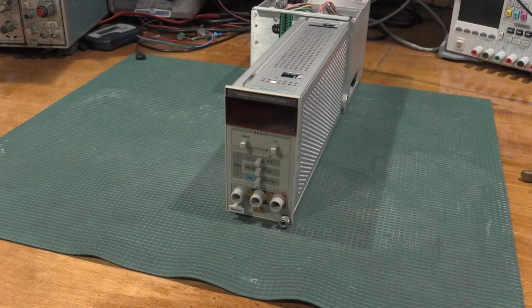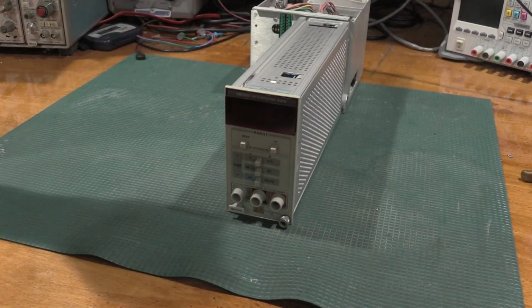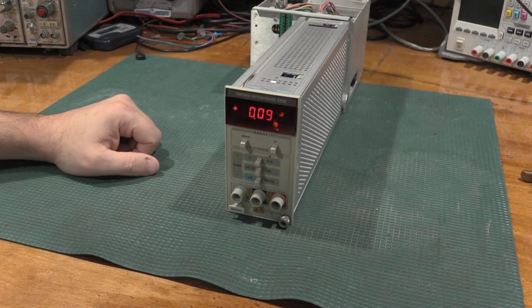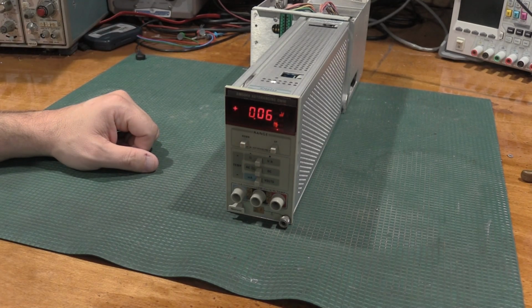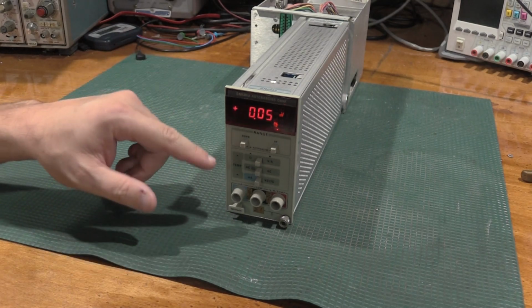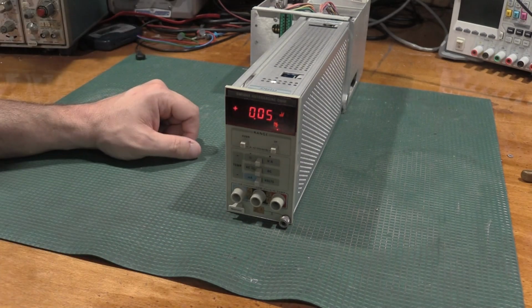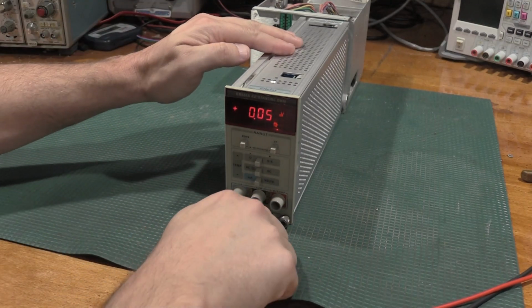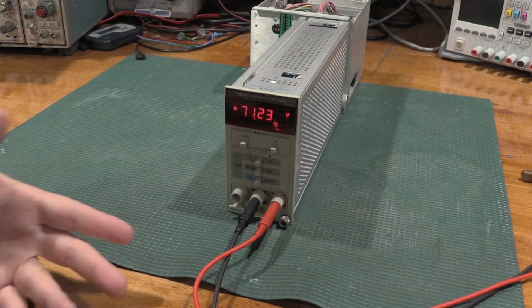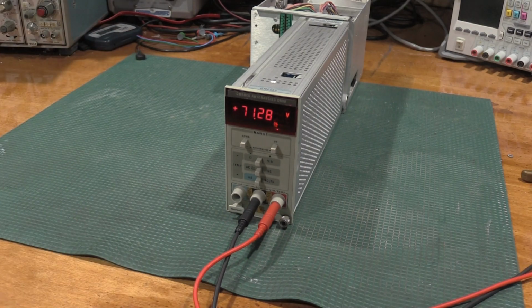Okay, here we are ready for a power up, and let's see what ultimately happens. So we got 71.5 volts from a random power supply over that way on some test leads, at least so says my DM502, which is repaired and in calibration. So this looks all good and healthy. Let's pop this voltage in. 71.2 with no warm-up, so I can't complain there. It's off a little bit, which we knew it would be, so calibration is necessary.